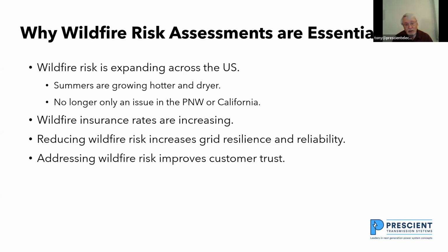And the wildfires do present a challenge to grid resilience and reliability. I think it was two summers ago now, we had a large amount of wildfires in the Pacific Northwest, and the wildfires put so much debris on the Oregon-California intertie. Now, this is three 500 kV lines that start in Oregon and terminate in California. They're on approximately a 10-mile difference between the right-of-ways, and all three of those lines had to be taken out of service at the same time because of debris coming down from wildfires.